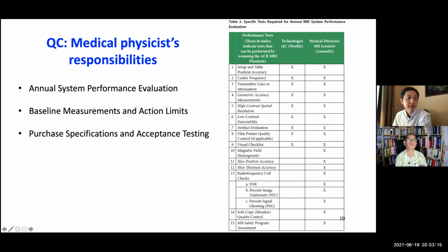Okay, about physicist responsibility. I have mentioned this table already. So physicists need to do annual testing of all the weekly testing plus the additional testing. So that's the annual system evaluation. But besides that, our responsibility also includes establishing baseline and action limit for the technologist QC. Our responsibility also includes purchase specification and acceptance testing. So I have mentioned items for acceptance testing.